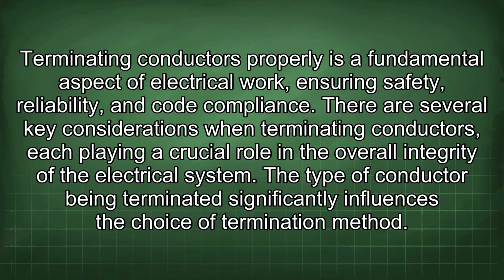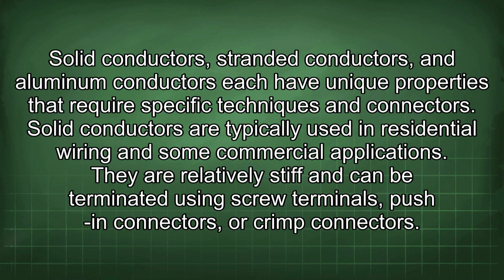system. The type of conductor being terminated significantly influences the choice of termination method. Solid conductors, stranded conductors, and aluminum conductors each have unique properties that require specific techniques and connectors. Solid conductors are typically used in residential wiring and some commercial applications. They are relatively stiff and can be terminated using screw terminals, push-in connectors, or crimp connectors.